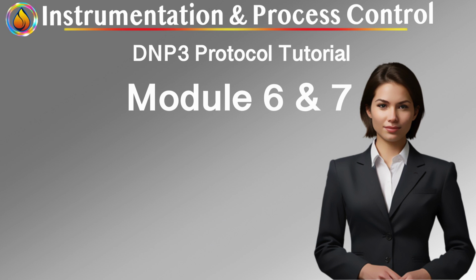7.2 Error Detection at the Link Layer, Cyclic Redundancy Check, CRC Strategy. The DNP3 link layer employs a high-granularity CRC mechanism designed specifically for noisy links. Key characteristics: CRC applied to the link header, CRC applied to every 16 octets of data payload, independent CRC blocks within a single frame. This design ensures that localized bit errors can be detected without discarding entire frames unnecessarily.